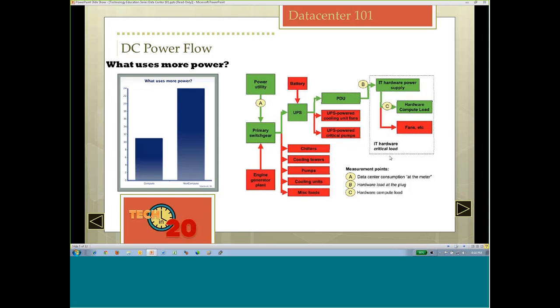It may also do some step down, but also, whenever that switchgear happens, there is a spike or a lack there, where the power is gone for a split second. If you didn't have something standing between that and your compute environment, the machines would switch off for a split second, and then everything would reboot, so your whole data center would reset itself. So you need a way to switch over without the data center, the compute equipment, noticing what happened. That's what the UPS is going to do for you.